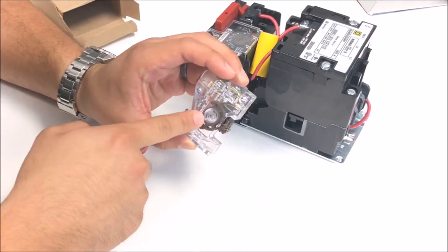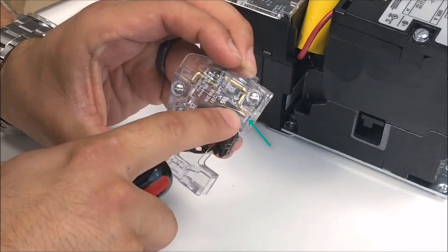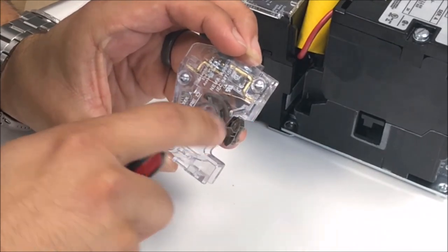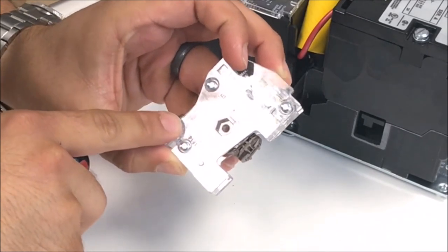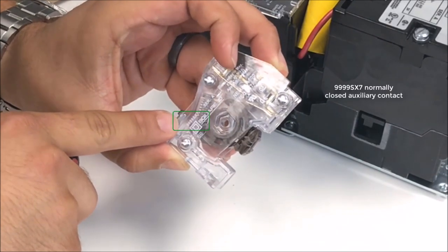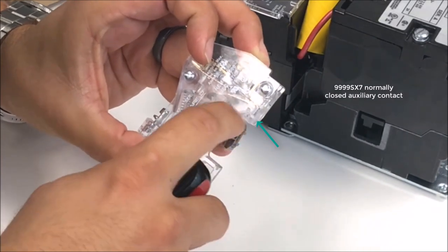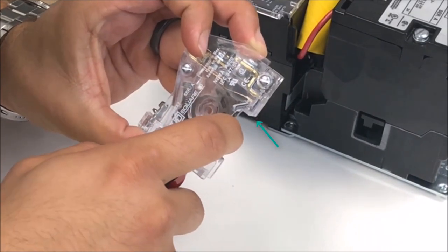These blocks are transparent so you can actually see if the device is normally closed or normally open. They have the printed part number on the device. This one's a 9999 SX7 which is a normally closed. You can see the closed contact here. Operate the device, it opens up.